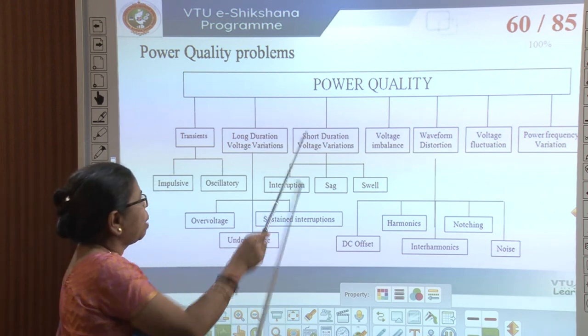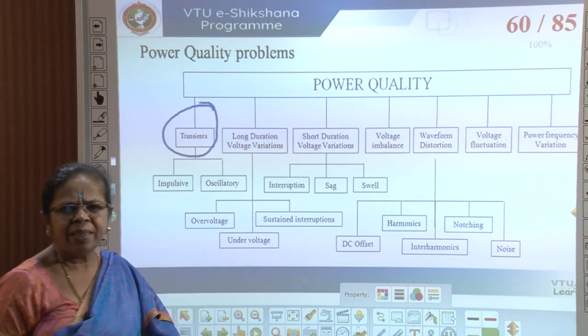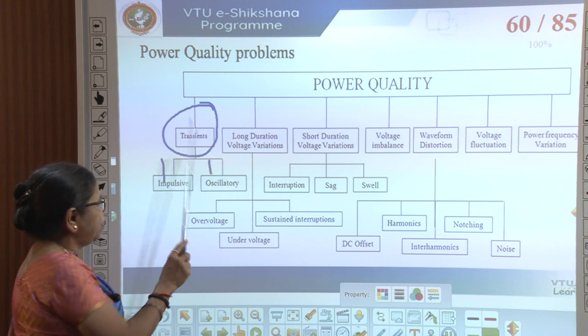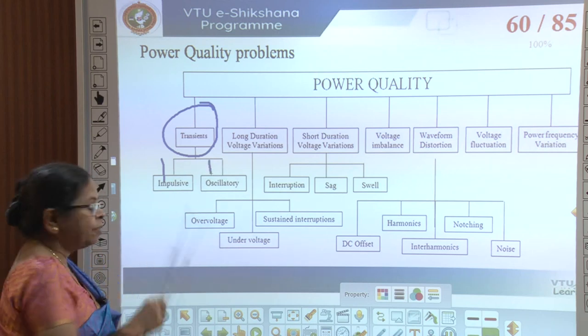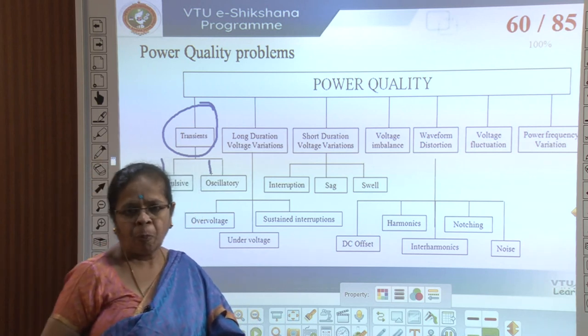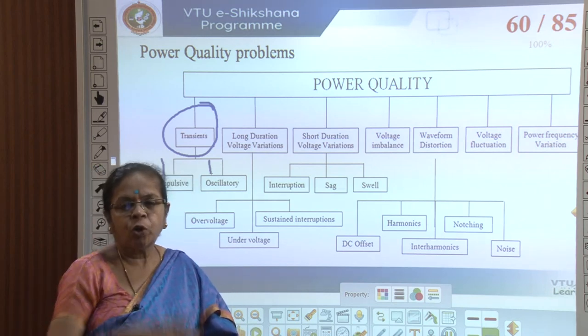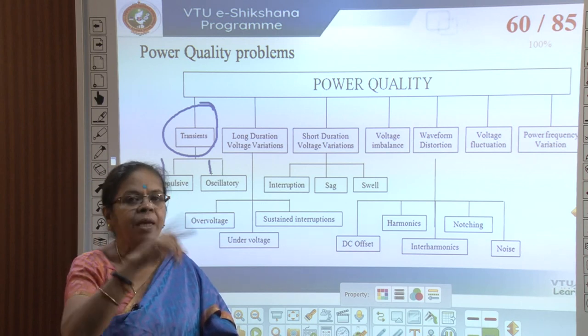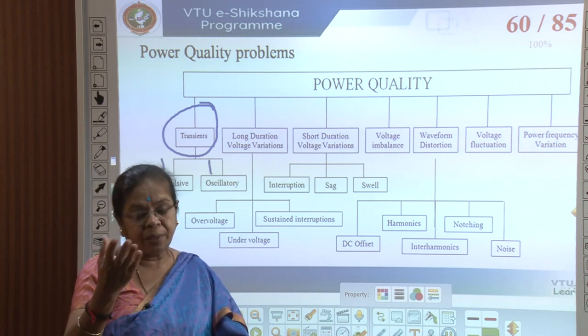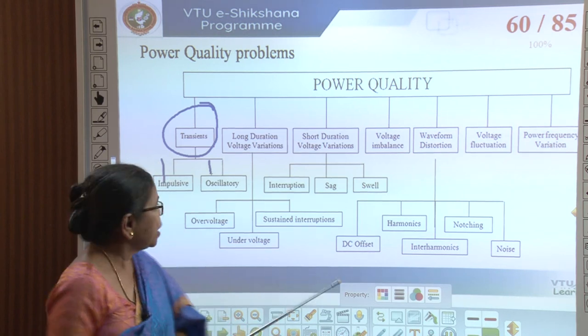Let us look at some power quality problems. The first is transients — a very short duration disturbance. Transients can be impulsive or oscillatory. An impulsive transient is a sudden non-power-frequency change typically caused by lightning — a sharp rise and then decay. An oscillatory transient occurs when switching on a capacitor: the existing R and L in the line create an RLC circuit which under certain conditions produces sustained oscillations.